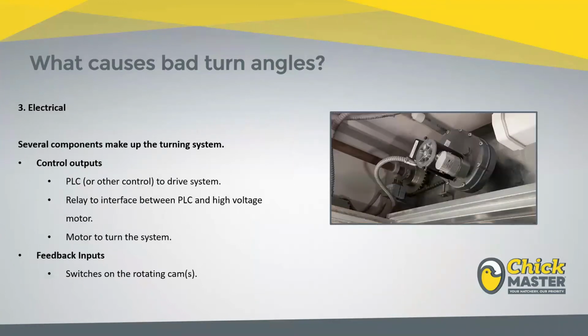Now, an electrical breakdown on a classic machine is actually fairly simple. There's very few control components within this machine that can go wrong. So from a control output point of view, you've got your PLC, or whichever control platform you've got in that machine, and that's what tells the turning system, once an hour or whatever you've set that duration to, to physically turn the machine until it sees that limit switch. Because the PLC is a low voltage and the motor on this is a high voltage, you've then got a relay interface that translates that low voltage signal to a high voltage signal, and then you've got the motor inside the machine itself. So really, you've only got 3 components there to physically get the machine to turn.